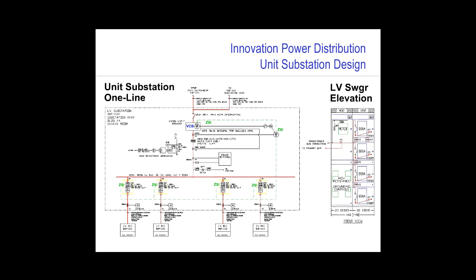I would also include the ARMS feature in each of the 4 secondary feeder breakers, allowing me to set up a maintenance mode so that operators working in downstream energized equipment could work in lower level PPE in the maintenance setting. Finally, you'll notice on this one line I've also included a dotted green line that connects the primary breaker with all of the secondary feeder breakers in a zone selective interlocking scheme, so that in the event of a fault within the zone, the breaker nearest the fault will trip without any intentional delay.